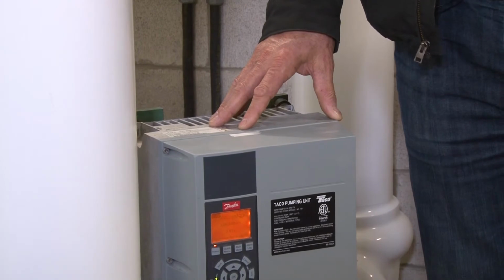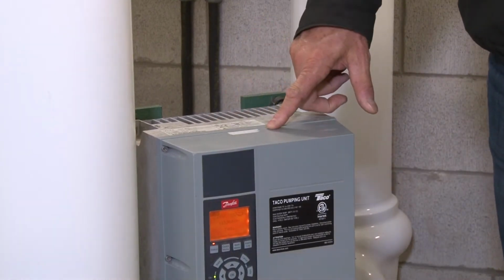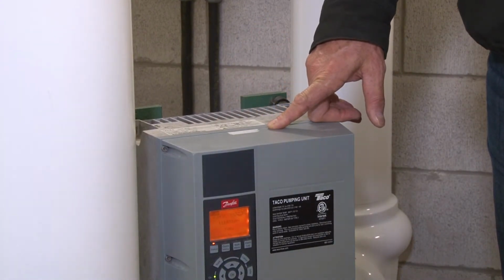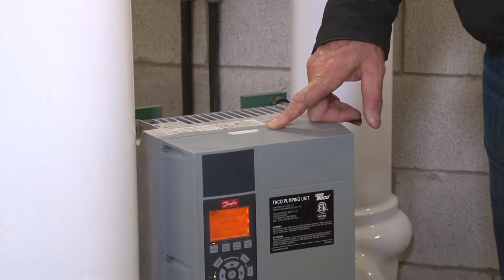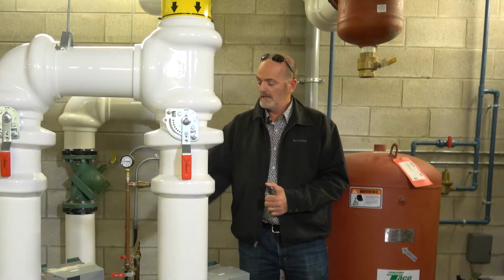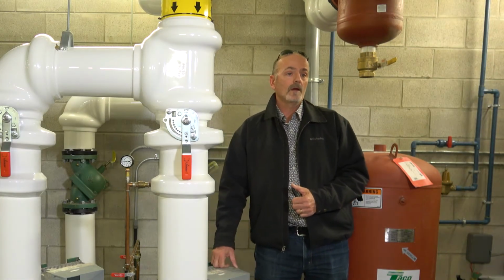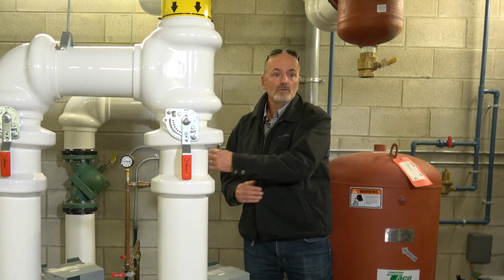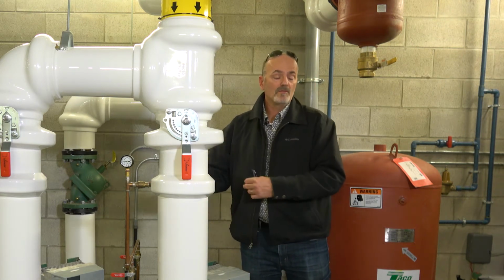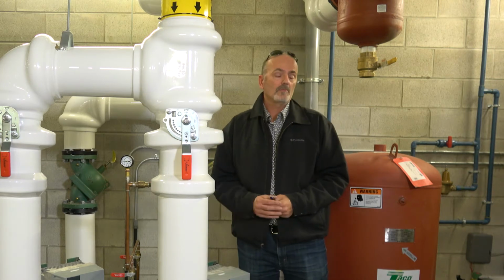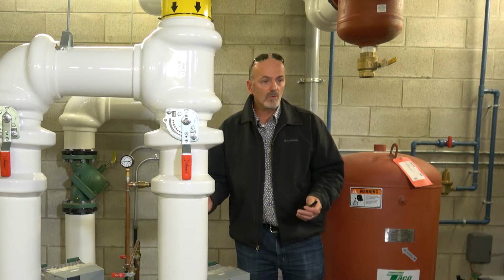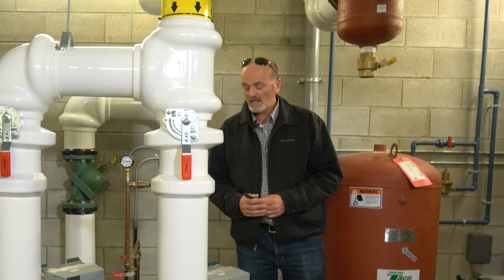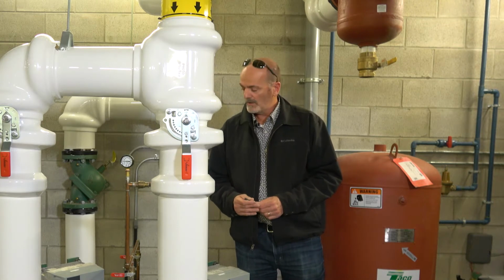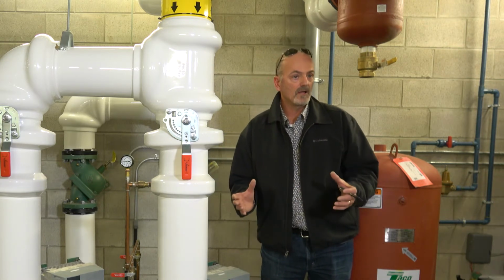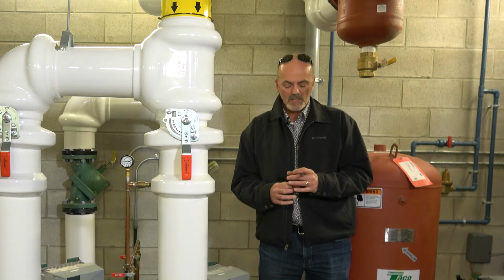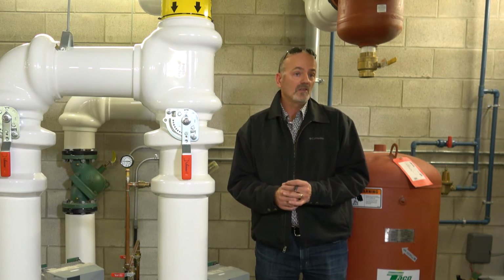As time clocks off on this drive, it has an internal clock as well that's in the programming embedded. It says, okay, I'm going to shut myself off and we're going to turn this one on. Okay, so it's called lead lag duty standby, and that rotates back and forth, so both the pumps, motors, and wet ends get equal runtime and wear, as do the seals. And more importantly, the seal doesn't sit for an elongated period of time, so you don't get lubrication. It can dry out and stick.